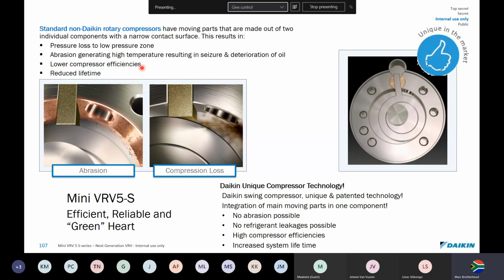You're going to have lower compression efficiencies because of the bypass factor. The gases can bypass because this is only loaded with a spring. However, if you look at Daikin, we do not have these separate components, and there you can see bits of wear metal that eventually collect on the rim of this volute. Daikin, however, has a solid casting for our compression.